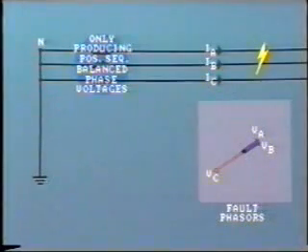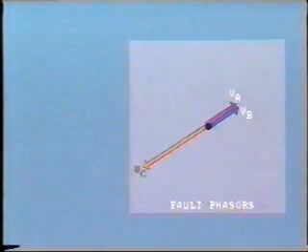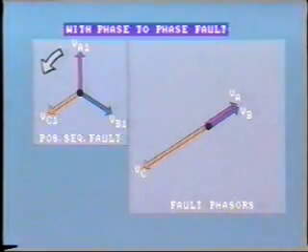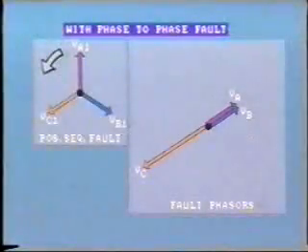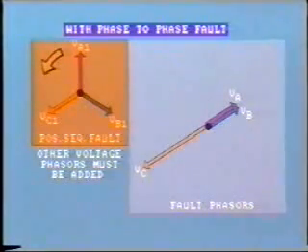The phase voltage on line C, that is VC, remains at its normal angular displacement, but A and B have been brought closer together by the low impedance of the fault. Remember, the generator, as always, is still producing positive sequence phase voltages. But at the fault, the voltage phasors look like this, with the different phase voltages being identified by VA, VB, and VC. The voltage at the fault on the unfaulted phase is approximately equal to its pre-fault value, and with our phase-to-phase fault, the positive sequence fault voltages are about 50% of this. Obviously, other voltages are present at the fault and are being imposed upon the positive sequence voltages — that is, other voltage phasors must be added to the positive sequence phasors to get fault phasors.